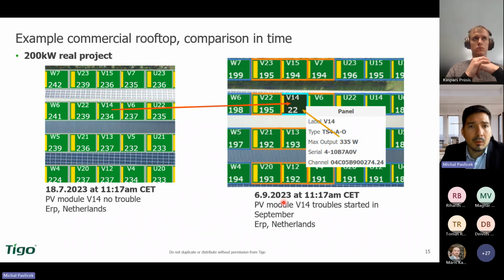If there are degradations, such as micro cracks or broken glass, you may sometimes also receive some error messages automatically. But for sure, the optimizer gives you a message that there is a broken bypass diode. So if, for instance, the PV module is losing 30% power, you immediately get a message showing you which module has an issue.